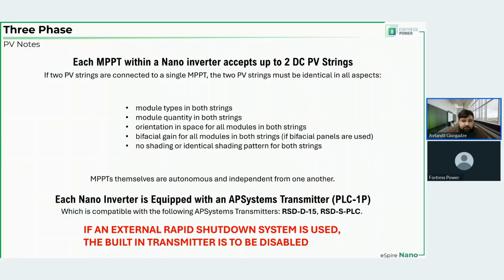Then I mentioned before that you can directly connect the PV strings here. That is true. And the reason why we're able to do that is because the transmitters are already built into the system. Namely, we have APS PLC 1P transmitters here in the factory in the Nano inverters. The compatible receivers, there's a typo there, which is compatible with the following AP Systems receivers, not the transmitters: RSD-D15 and RSD-S PLC.